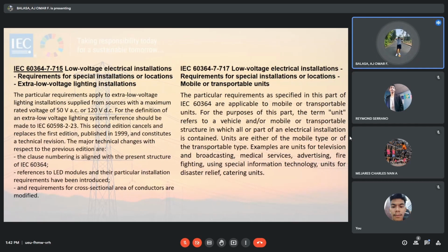Typically, the connection for the unit once delivered to site is normally not under the control of the person performing the initial verification. So the person responsible for the connection of the unit will need to check the relevant documentation provided and confirm the relevant requirements are satisfied before the unit is energized. Next.